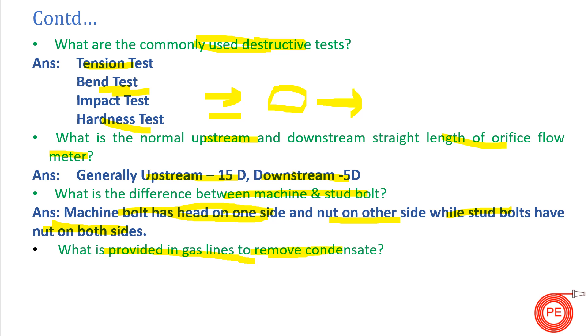What is provided in gas lines to remove condensate? This is important for steam, power plant, or steel plant interviews. Gas condensate is removed with the help of drip pots, which are generally installed on the lower portion of pipelines. The condensate moving with the gas gets separated by these drip pots. If this condensate or moisture enters equipment, it can damage the equipment or reduce burning efficiency.